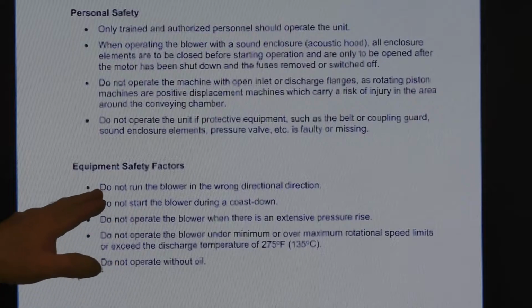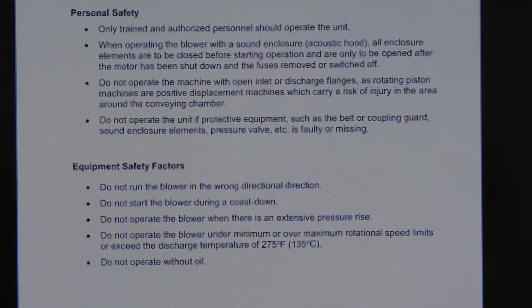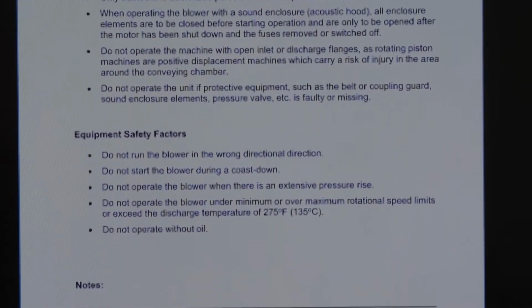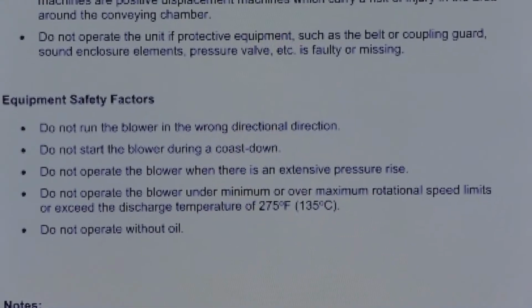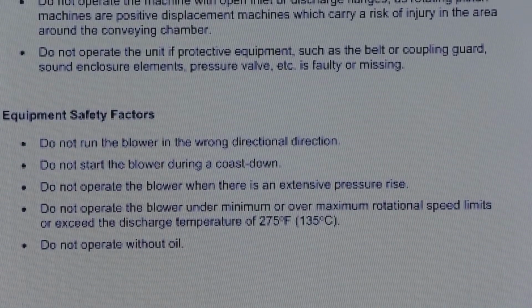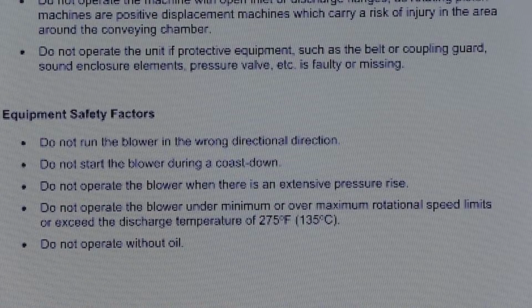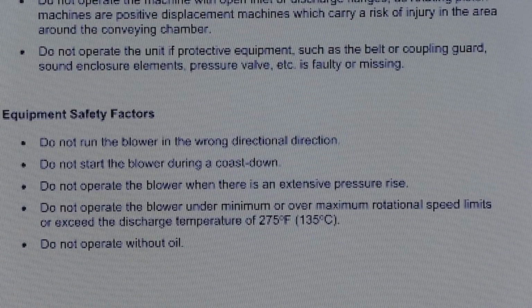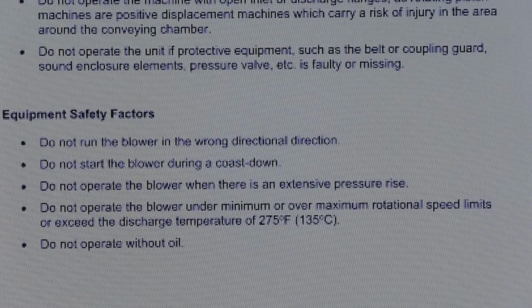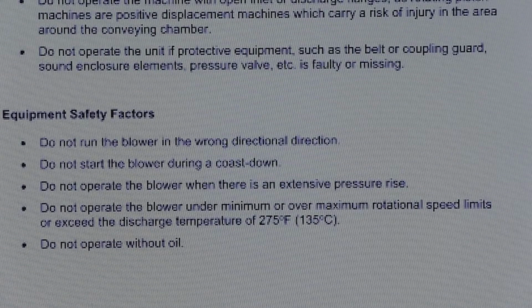Now here's a very important one. If you ever have to replace the motor, replace the drive, or anything electrically that can affect the rotation of the motor, you need to pull the belts off and verify motor rotation before you put it back in operation. Because if you run the blower backwards, it will damage and or destroy it.